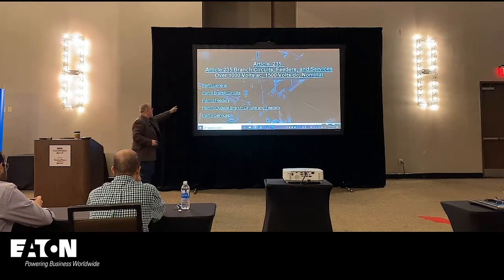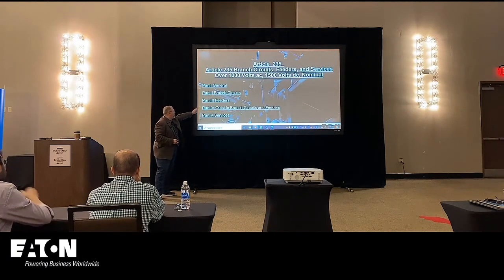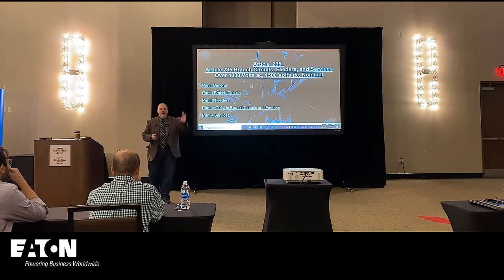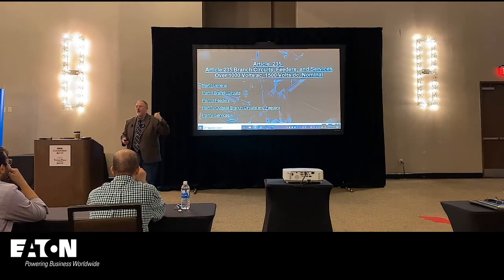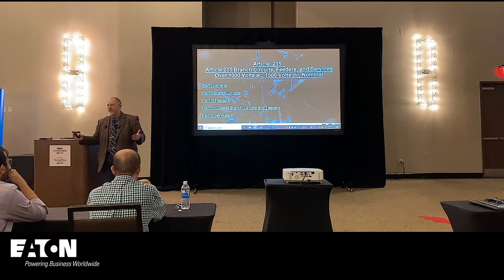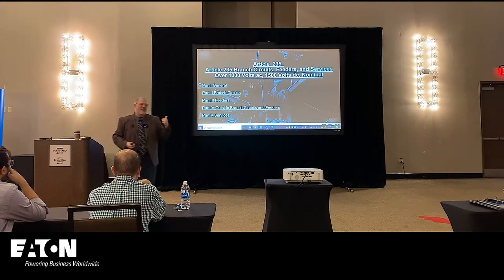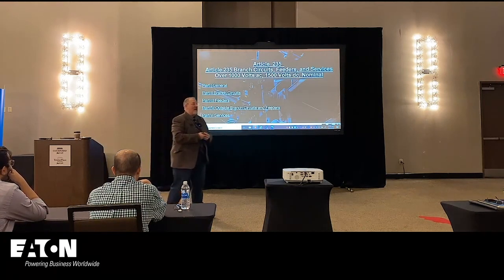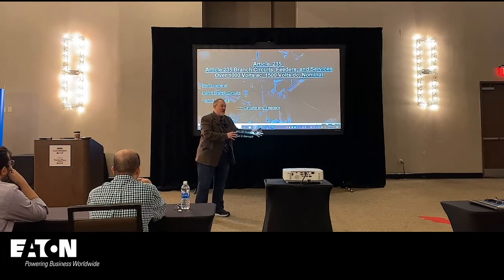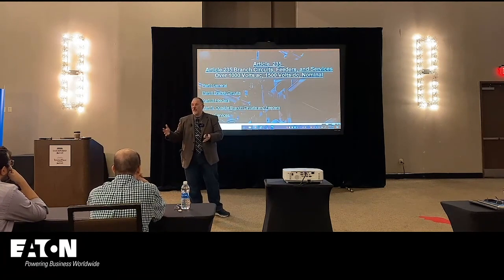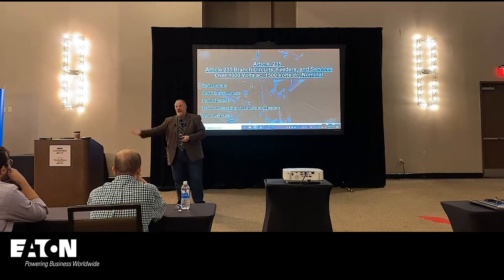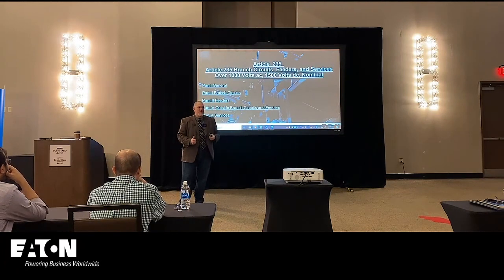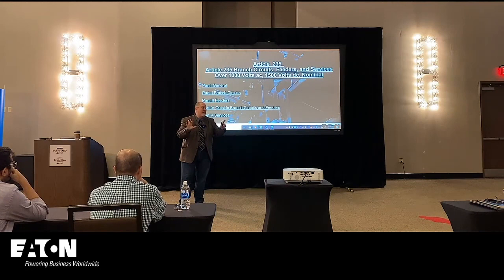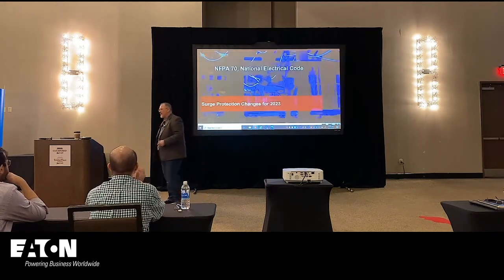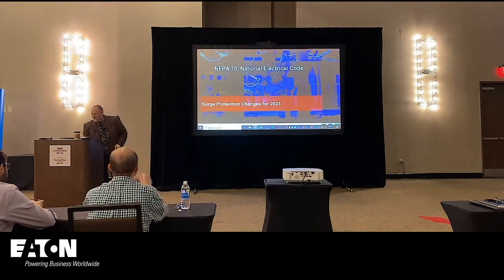There's your 235. So part 1, general, branch circuits, feeders, outside branch circuits and feeders, and then part 5 is services. So again, when you look at this article, it's existing language. And in fact, if you look at branch circuits, I chuckled a little bit because we simply moved stuff out of 210. So you'll see things in there about branch circuits for appliances, medium voltage appliances, which I thought was, boy, that's kind of ridiculous. But we couldn't make any technical changes. So we're going to clean it up this next cycle.